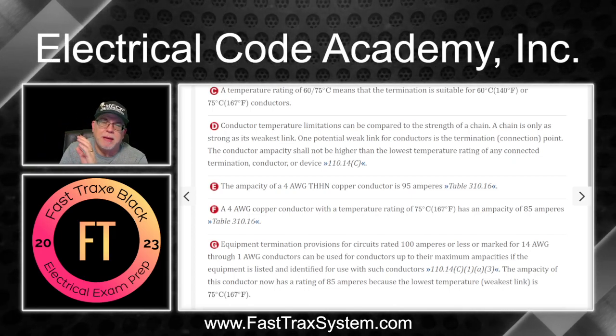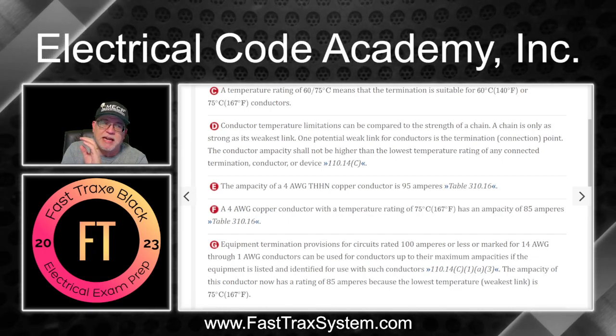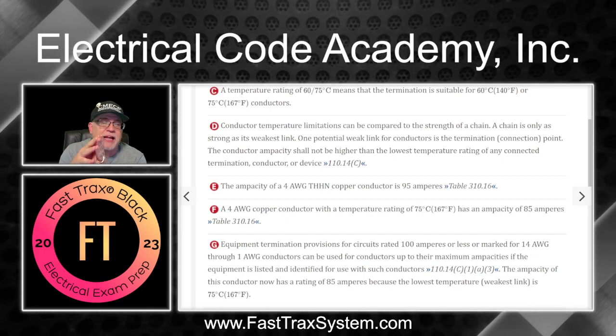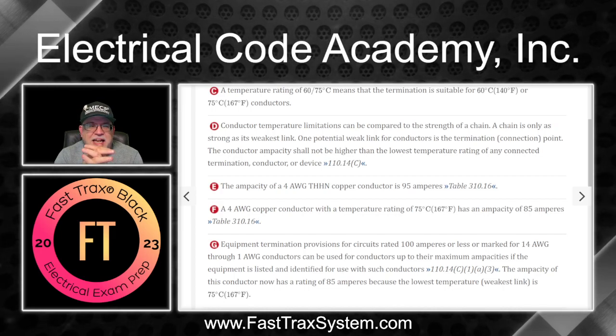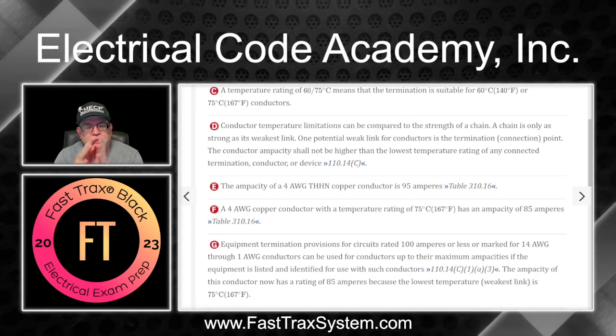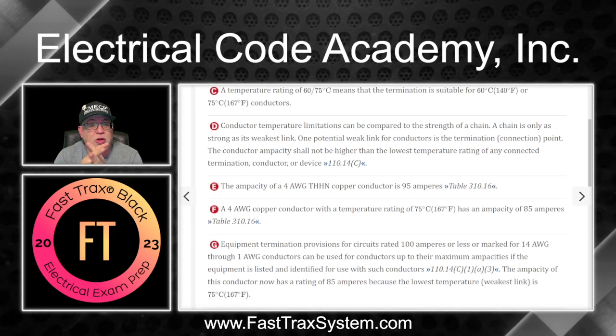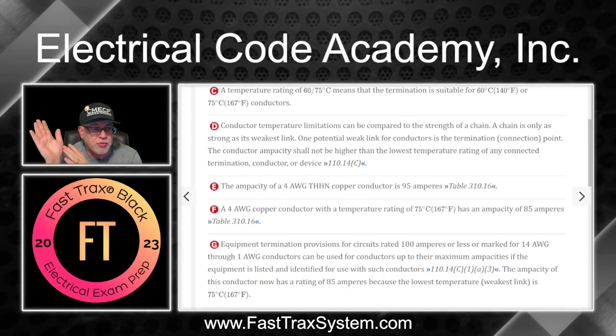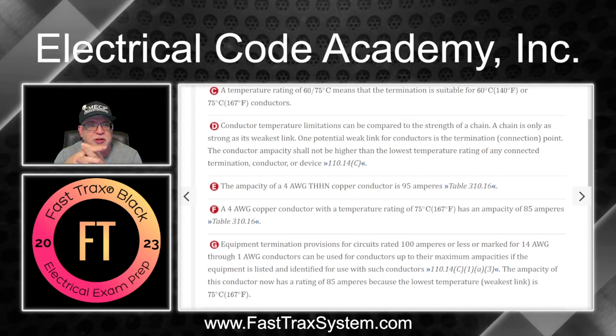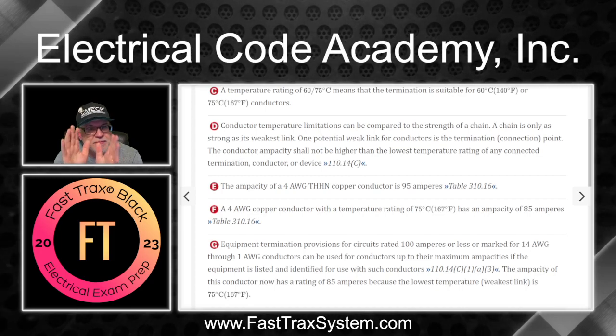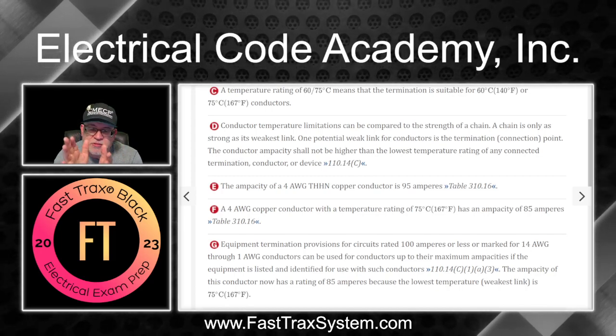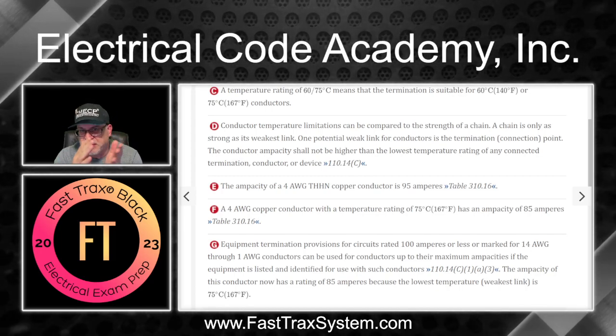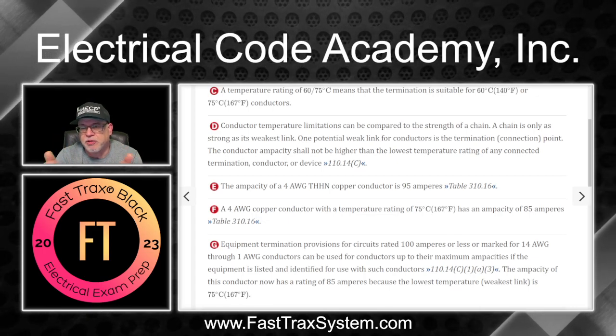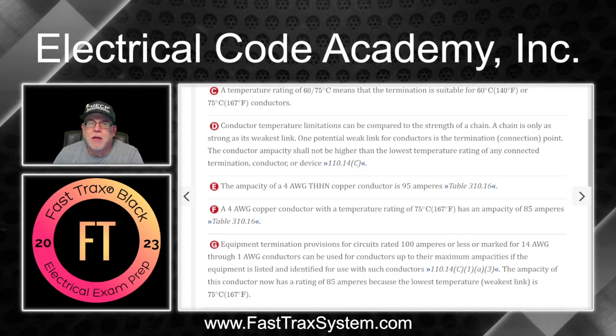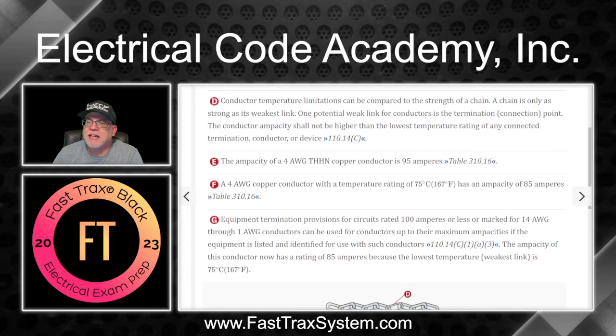You would still be able to use the 75-degree ampacity, except for, like I said, things like non-metallic sheath cable, which is going to ultimately lock you in at 60, even though you can do adjustment and corrections from the 90, but that's not part of this episode. Just remember, this is going to be very important when developing the weakest link theory of your ampacity of a conductor. All right, so the next one we're going to look at is E.